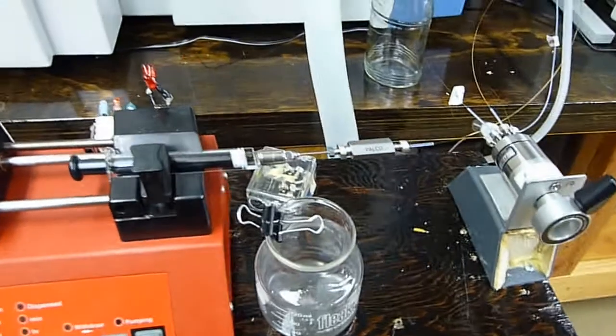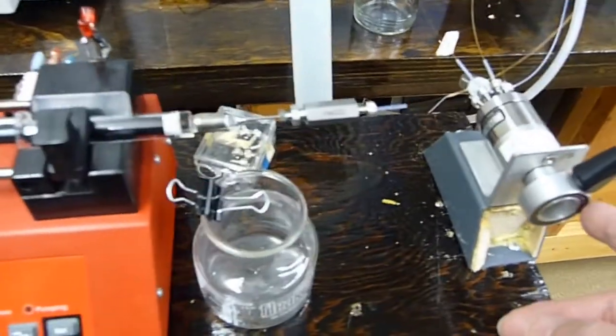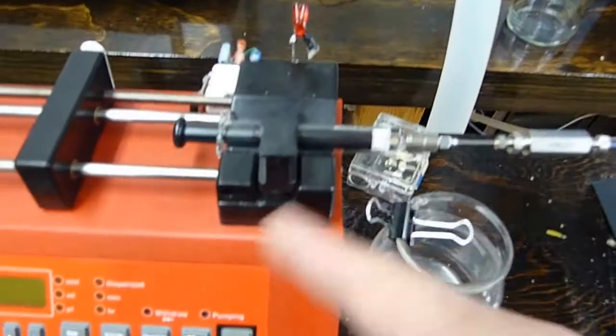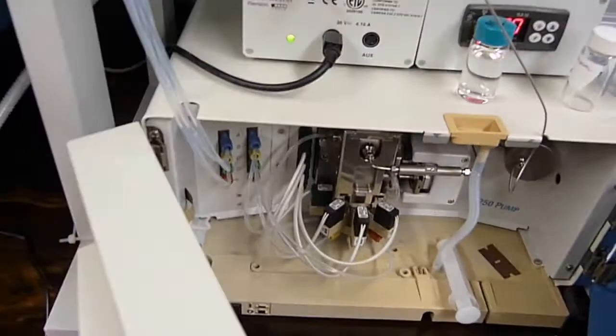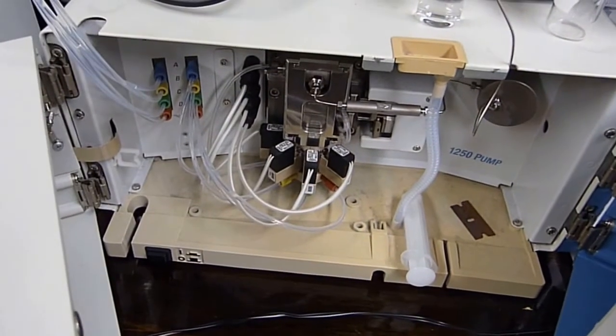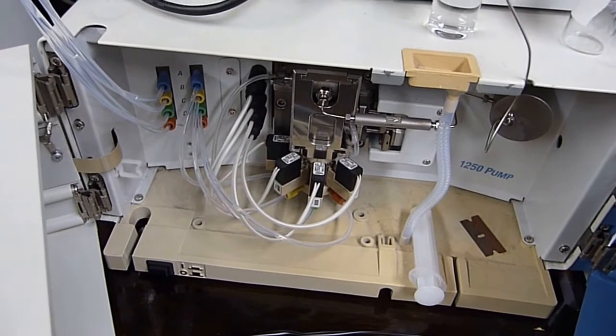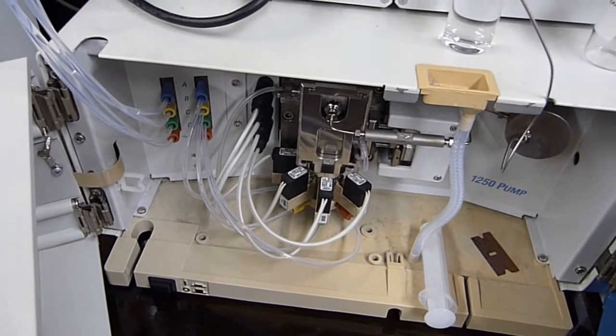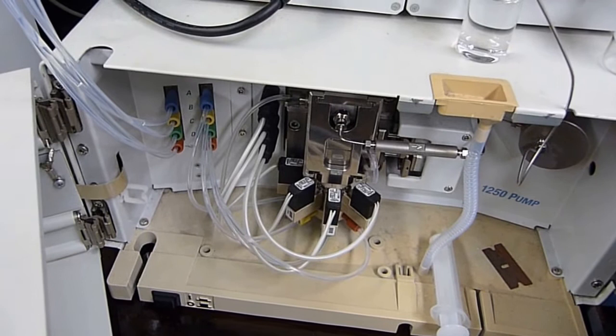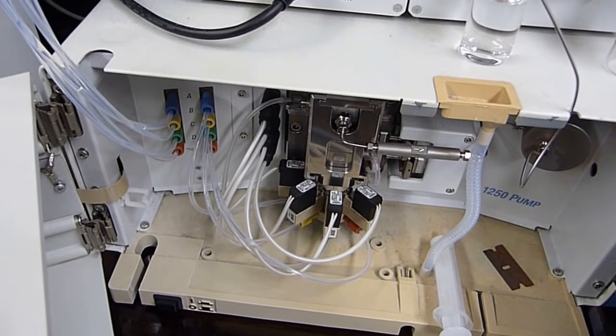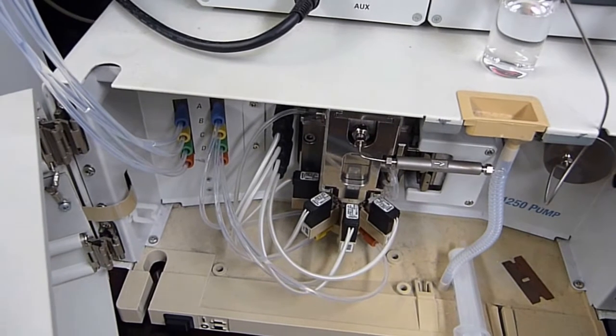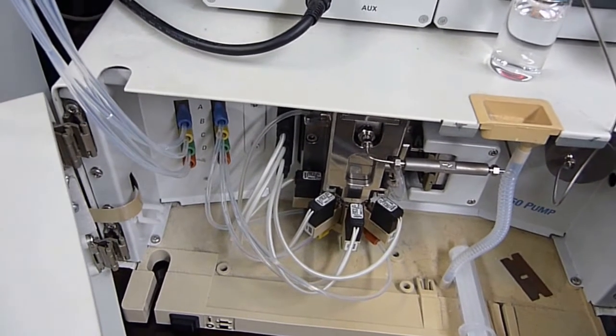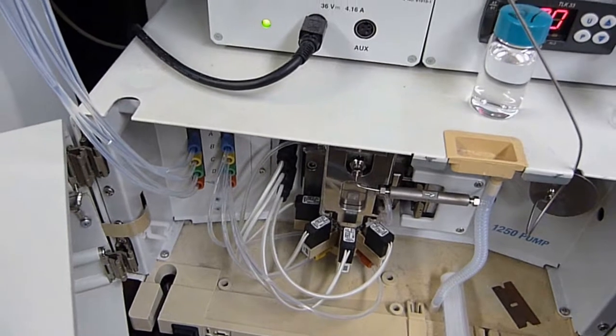And why go through the trouble of having a manual injection valve and a syringe pump? Well, there is great reluctance in our good HPLC solvent pump to be putting chloroform in here. What it would do to seals on a long-term basis. And chloroform is not acetonitrile. It's definitely more aggressive in my opinion.